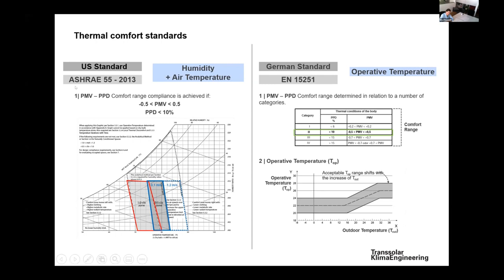The ASHRAE standard defines two zones on the psychrometric chart. In winter, comfort lies between roughly 70 and 80 Fahrenheit at specific humidity levels. In summer, a slightly higher temperature range is considered comfortable because you have fewer clothes on. In winter, you have more clothing, and in summer less, which is why the range is shifted slightly.